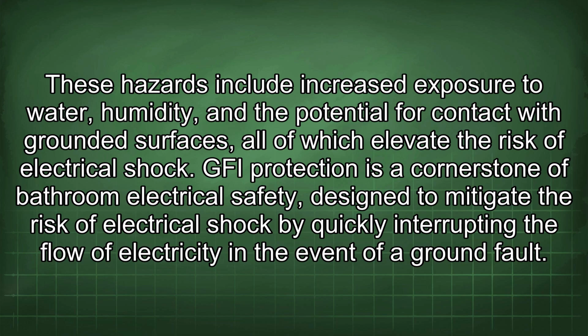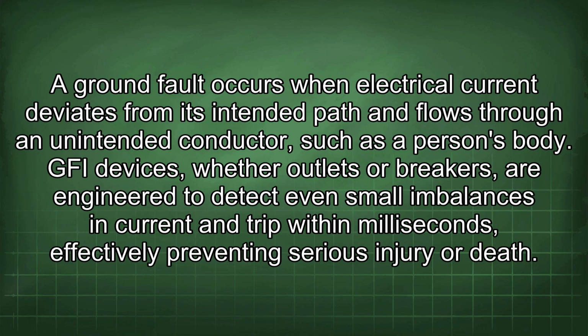GFI protection is a cornerstone of bathroom electrical safety, designed to mitigate the risk of electrical shock by quickly interrupting the flow of electricity in the event of a ground fault. A ground fault occurs when electrical current deviates from its intended path and flows through an unintended conductor, such as a person's body. GFI devices, whether outlets or breakers, are engineered to detect even small imbalances in current and trip within milliseconds, effectively preventing serious injury or death.